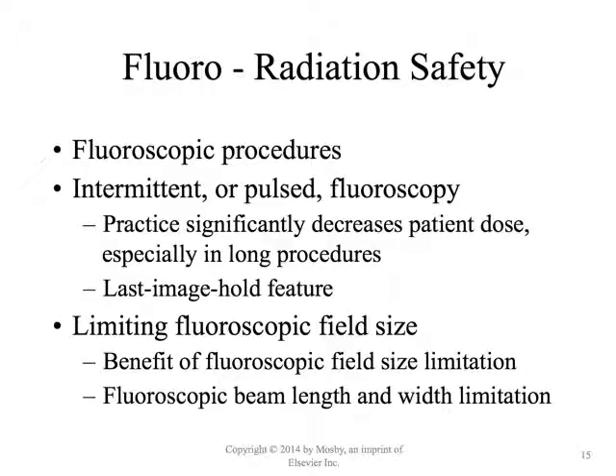All right, let's talk a little bit about fluoro. The things that we can do to decrease our occupational exposure and patient exposure when we're working with fluoroscopes is to use an intermittent or pulsed fluoro mode. It's fairly easy to toggle over to that. It does not typically affect the image quality all that much. As well as the last image hold feature. Most fluoroscopes that y'all work with now probably already have the last image hold preset into it. But we used to actually have to manually tell it to do that.